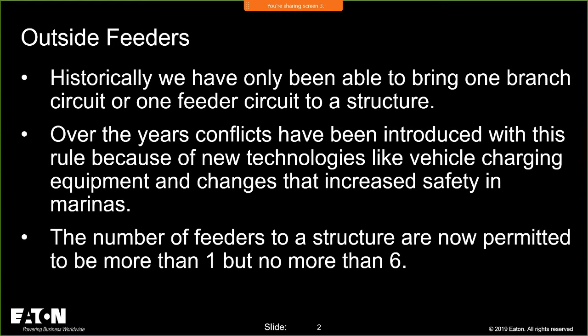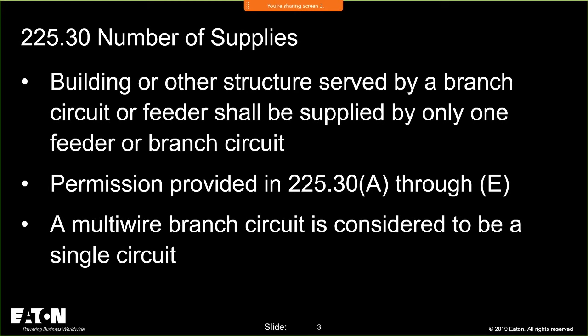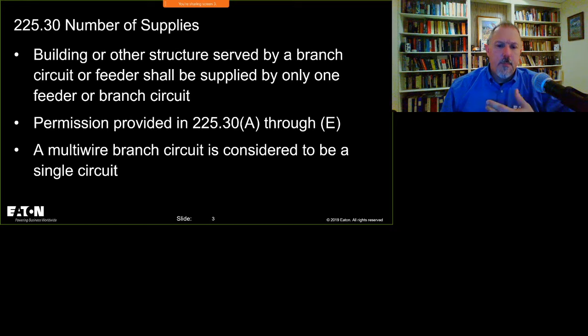Now, regarding the building or other structure served by a branch circuit or feeder, what you're seeing now is that you can bring multiple feeders out to these locations when you meet certain criteria, which we're going to talk about. So you have the ability to make some changes with regard to pulling more feeders out there.